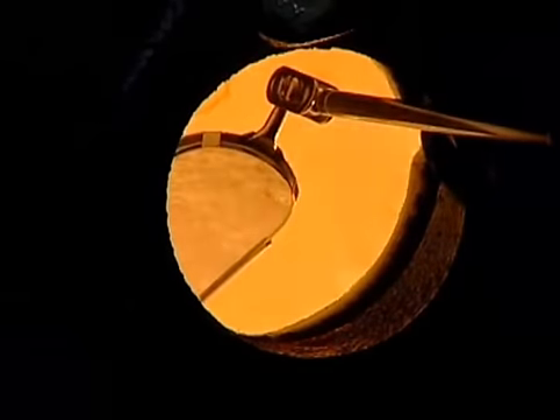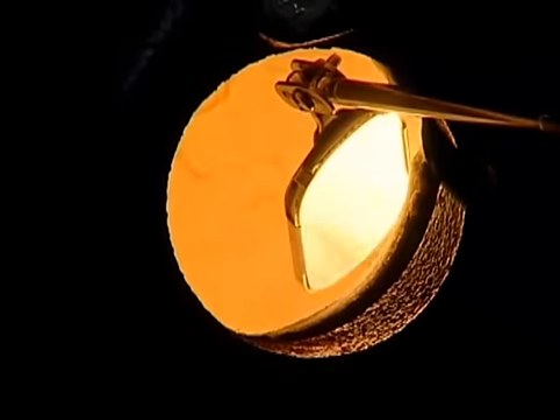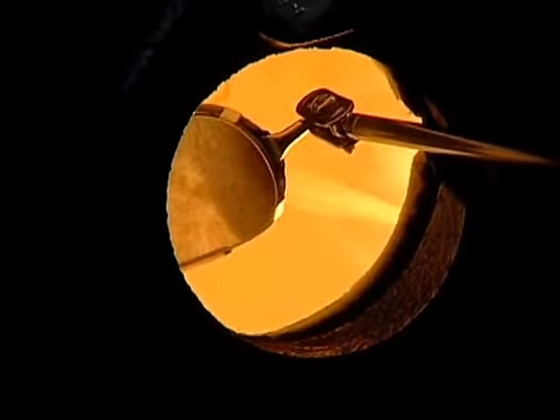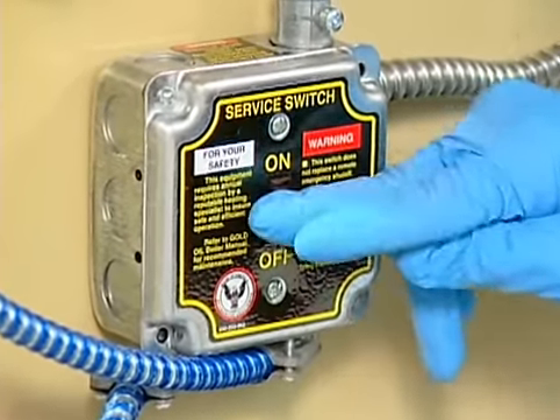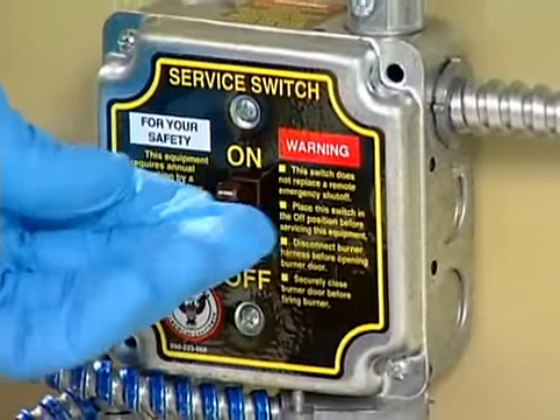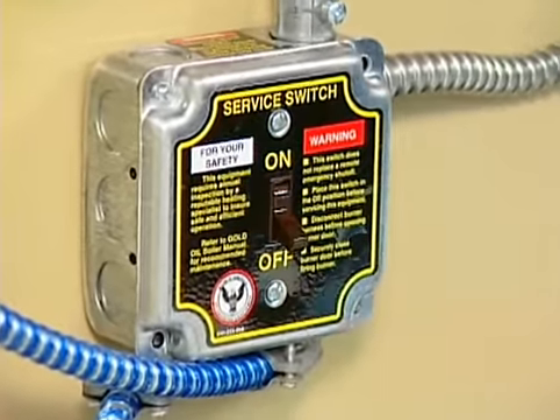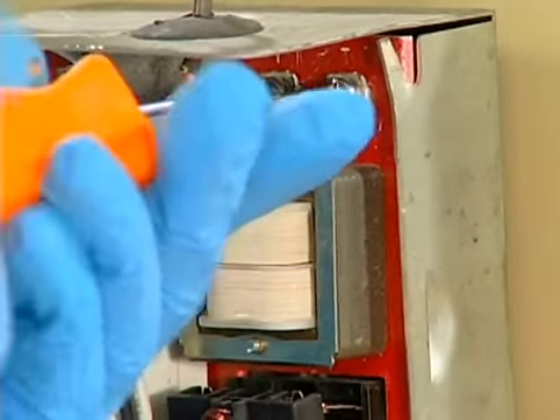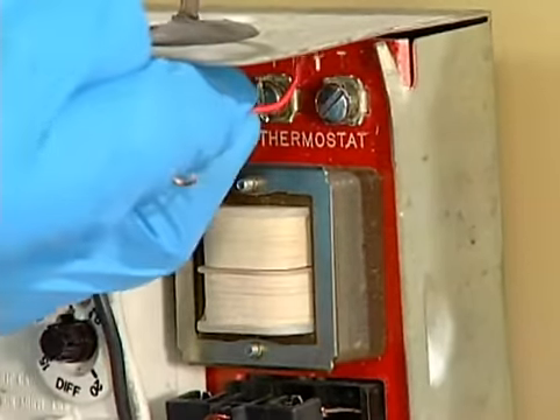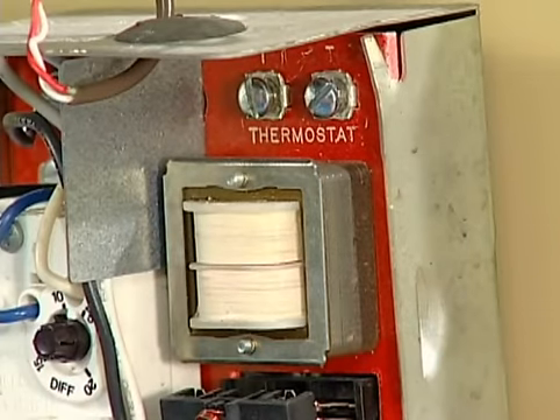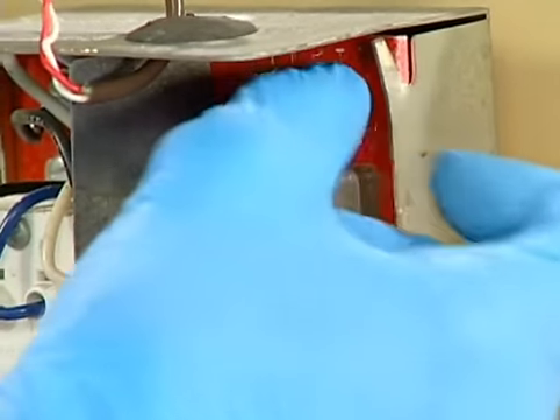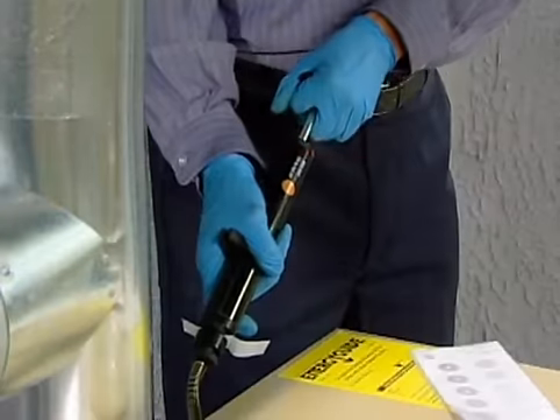Start the burner. Check the appearance of the flame and make sure that there's no impingement. Check the flame and combustion area with your flame mirror. Cycle the burner to ensure prompt ignition, smooth operation, and clean cutoff. Disconnect the thermostat leads and install a jumper across the TT terminals to keep the burner running. Check the operation of the high limit.